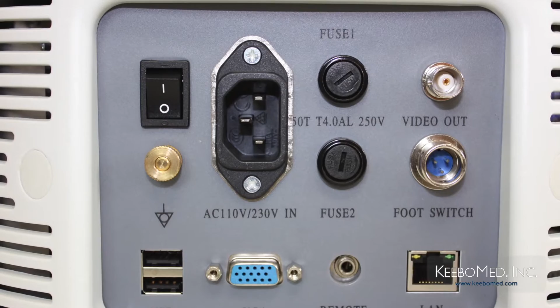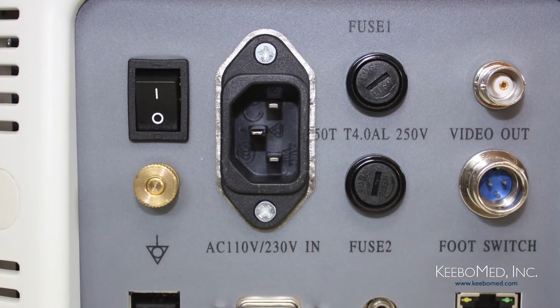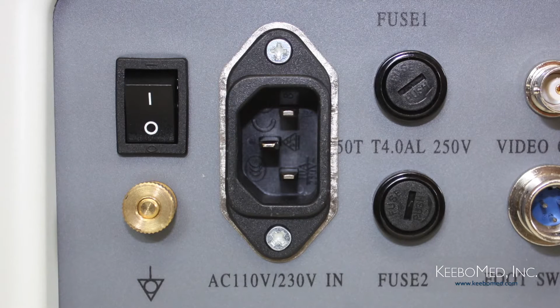It is important to make sure that the AC voltage matches the power requirements indicated on the system's label. Connecting the system to the wrong power supply may cause damage to the system and danger to the operators and patients. It is important to use the power cable that is provided to ensure proper function. The power cable that is provided is a 3-wire cable and uses a 3-pin grounded plug, which has a grounding terminal. Follow these simple steps to connect electricity to the ultrasound.